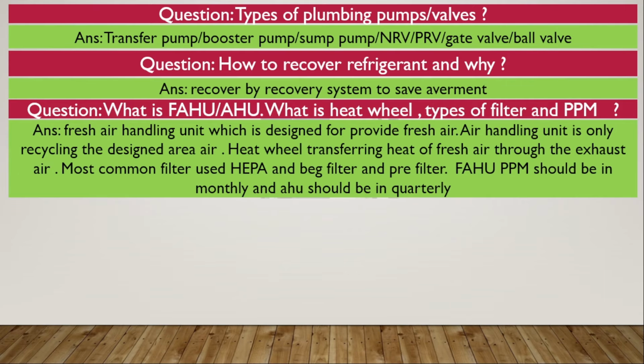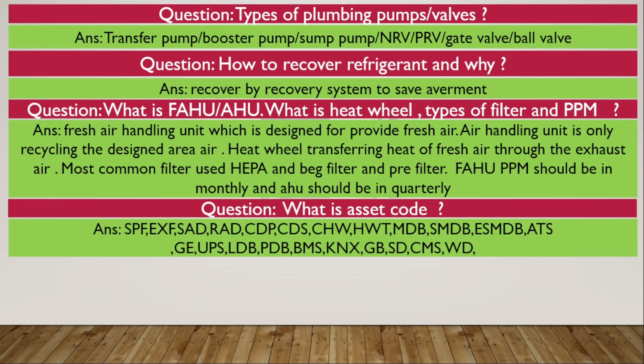So FAHU, fresh air handling unit, is designed to provide fresh air in the building. AHU, air handling unit, only recirculates air in the designed area. Heat wheel transfers heat of fresh air through the exhaust air. The most common filters used are HEPA filter, bag filter, and pre-filter. FAHU PPM should be monthly and AHU should be quarterly.